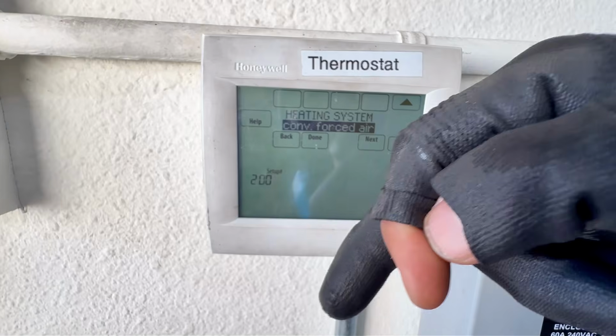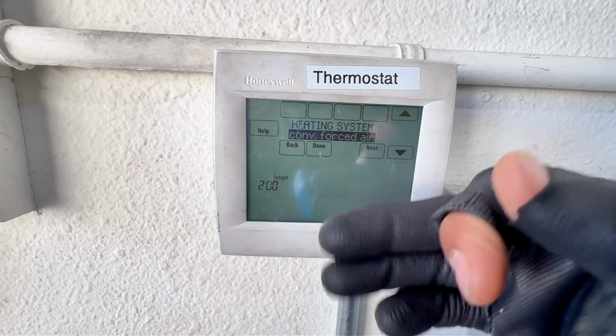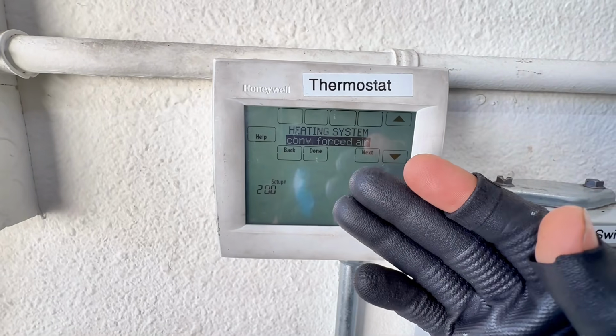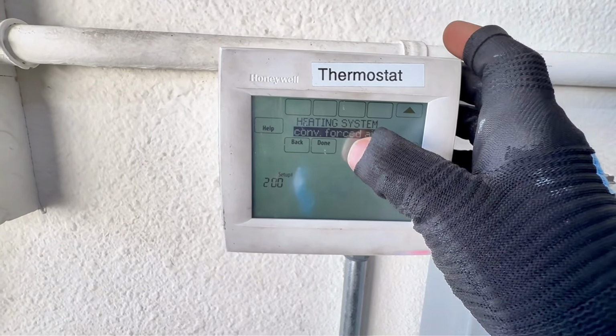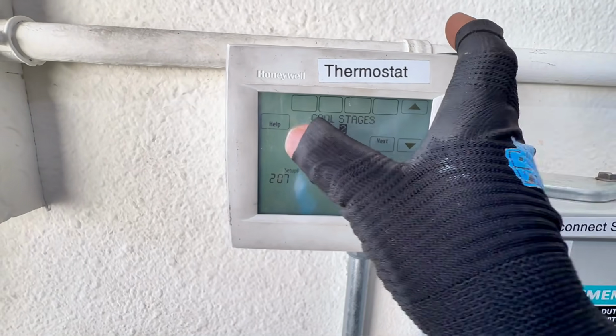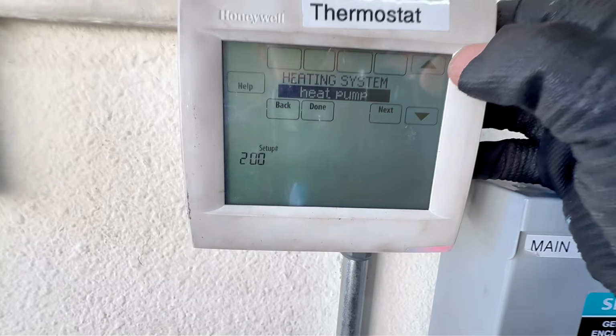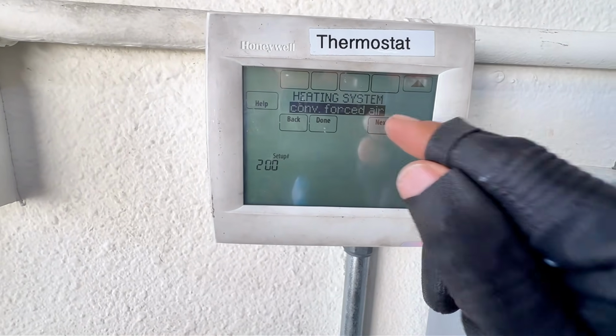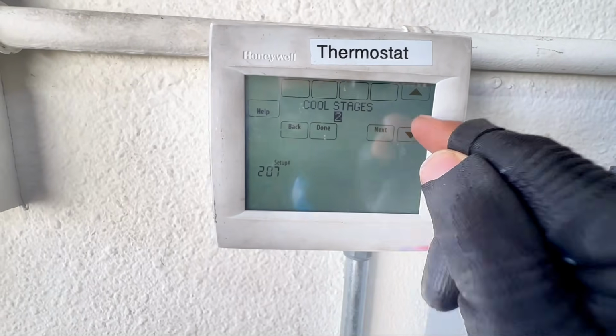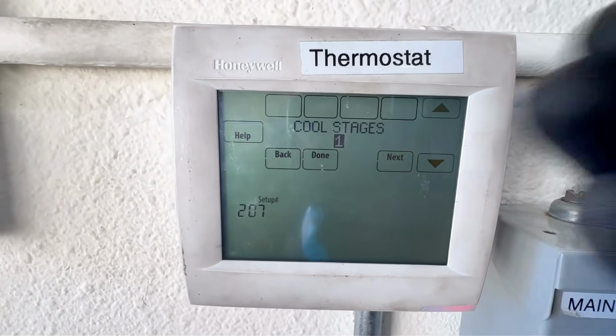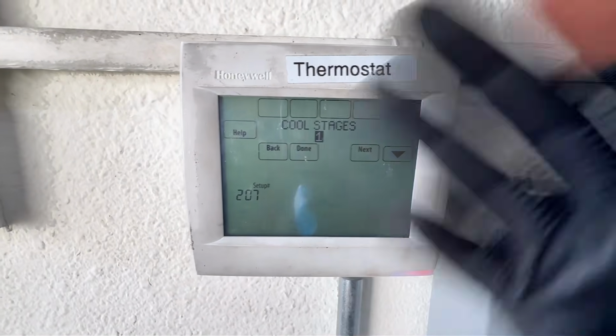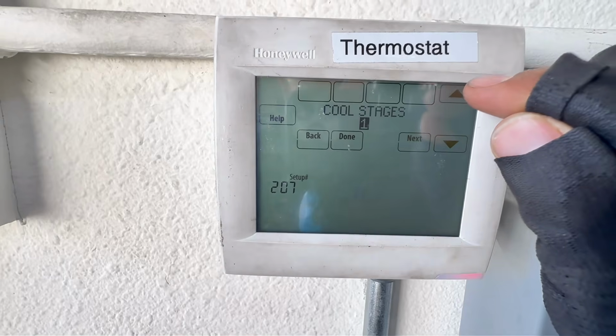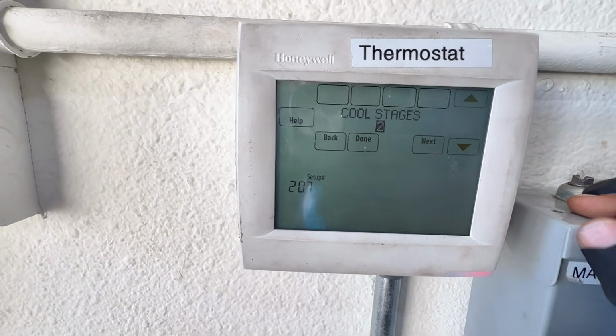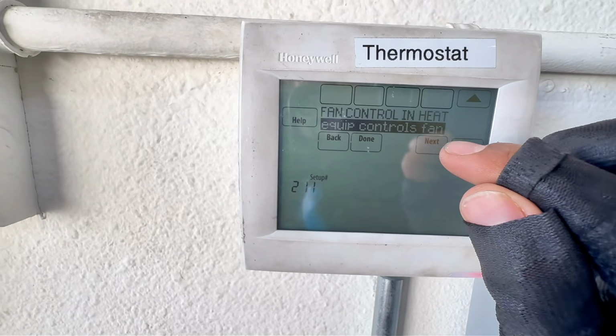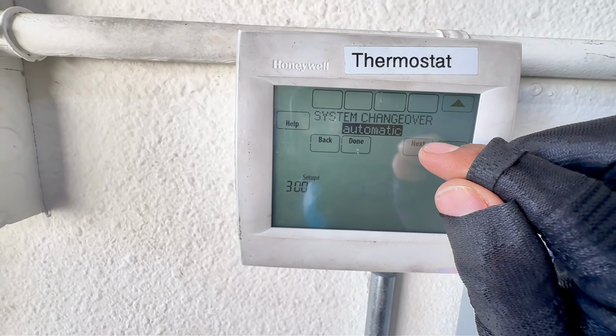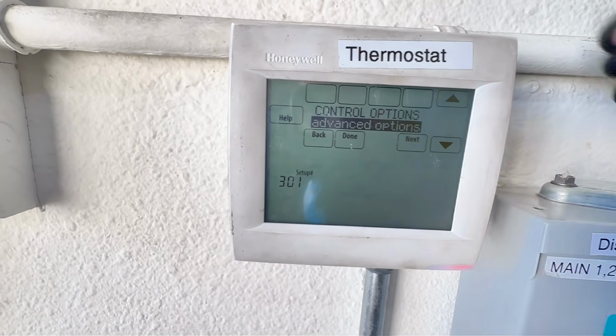So on this specific package unit, this is a stage 2 cooling with stage 1 heating, but it's not a heat pump. It's using gas. So for heating, you would have to put conventional forced air. This is where you would change it if it was a heat pump or not. You see, heat pump now. But it's conventional forced air. So this is where we're going to get to, stage 2. Right there, you have to put that it has 2 stages. You actually have to do that. If you don't, then that's it. It won't work with stage 2 cooling. So you have to first do stage 2 cooling. That's the first step. The next step, at least with this specific thermostat, you're going to go to, right here, control options.